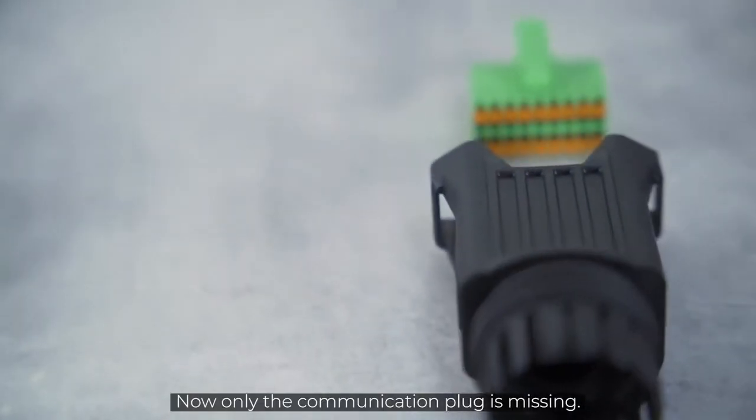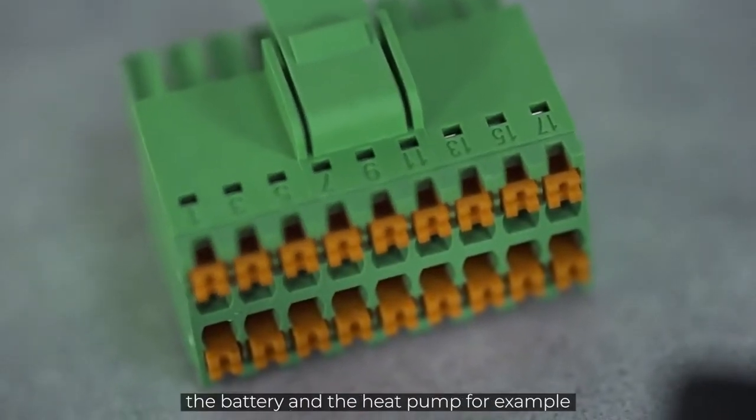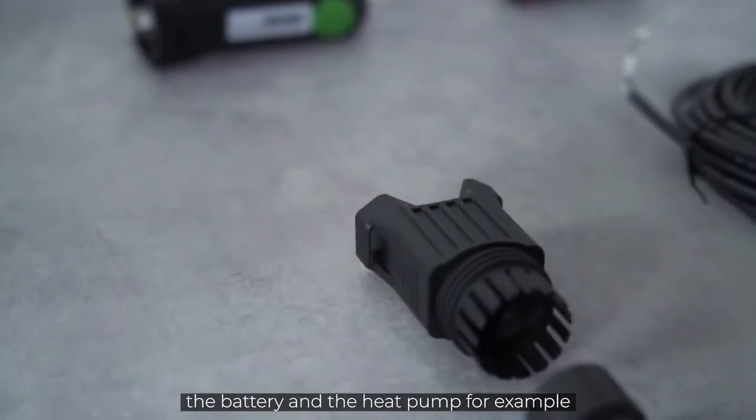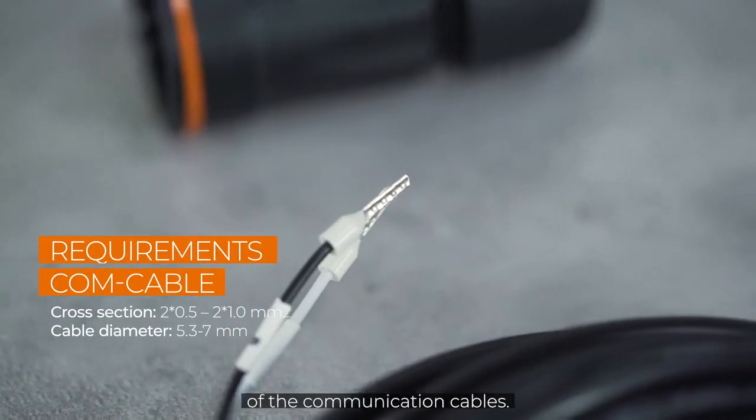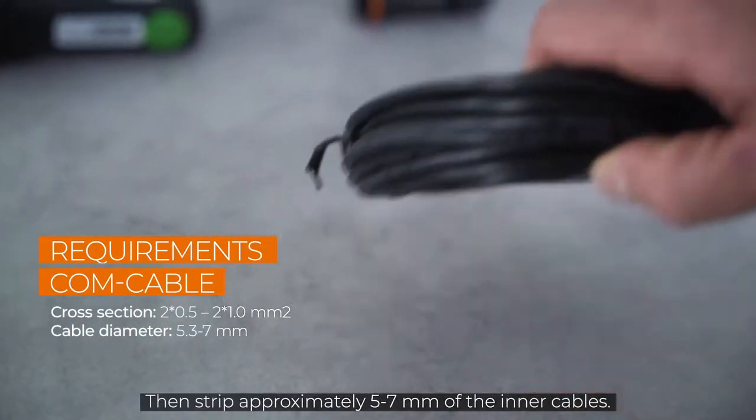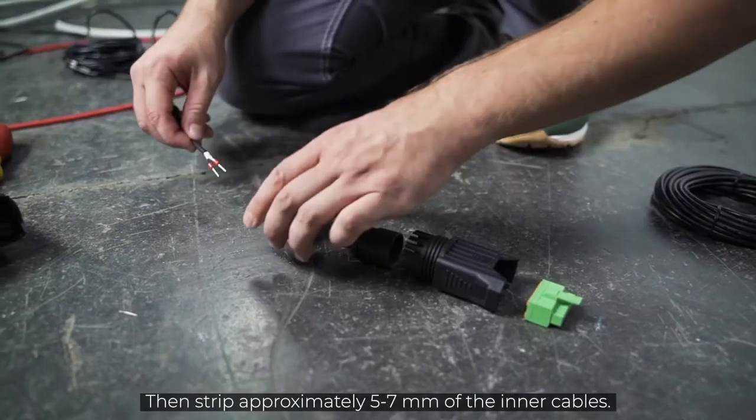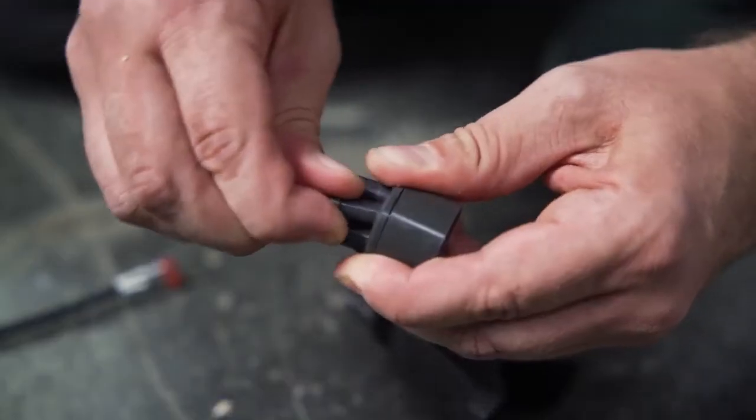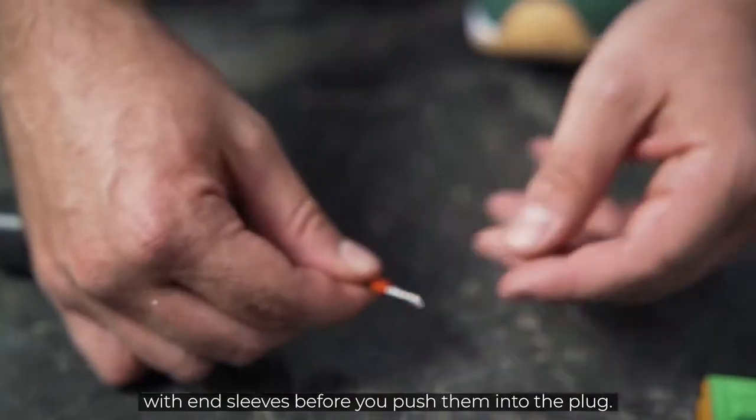Now only the communication plug is missing. The smart meter, the battery and the heat pump for example, are controlled via the communication interfaces. Remove approximately four to five centimeters of the cable sheath of the communication cables. Then strip approximately five to seven millimeters of the inner cables. If necessary, you may have to fit the cables with end sleeves before you push them into the plug.